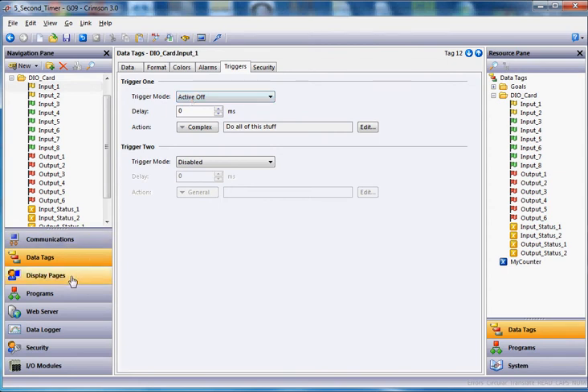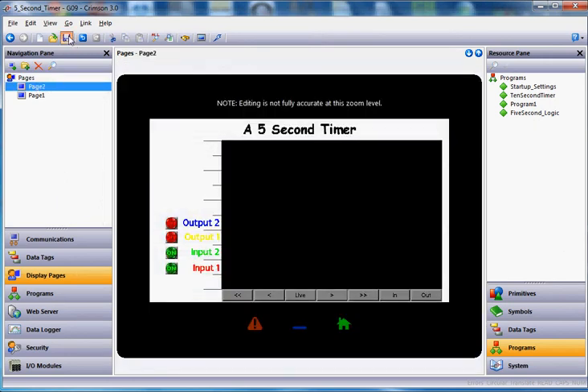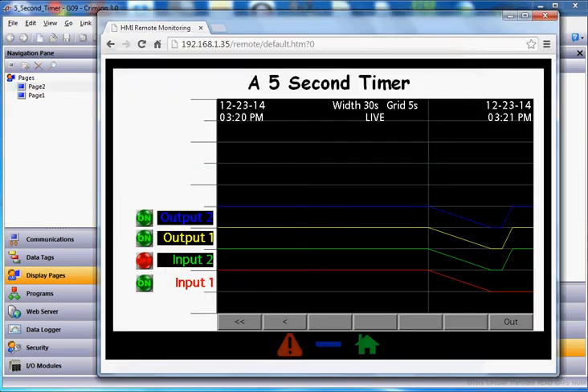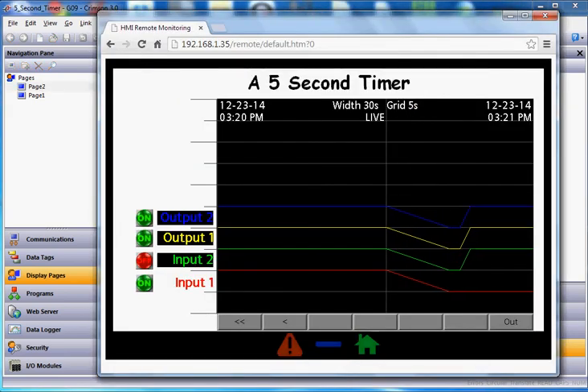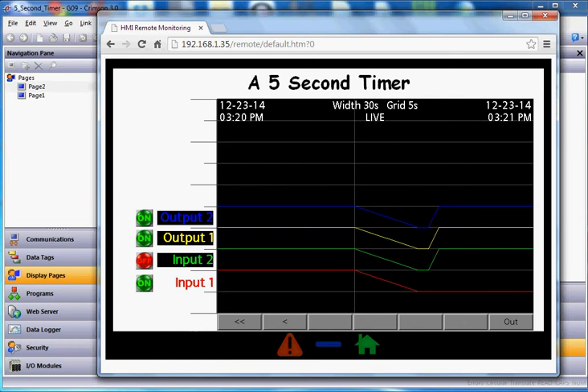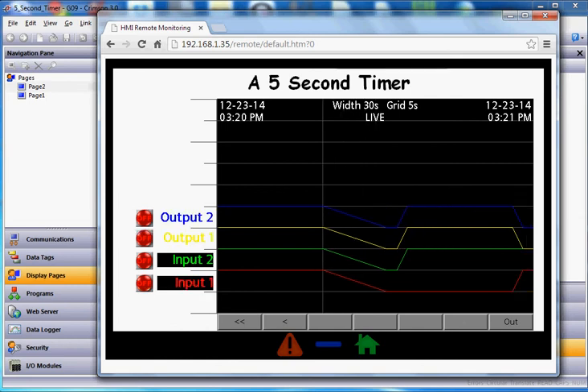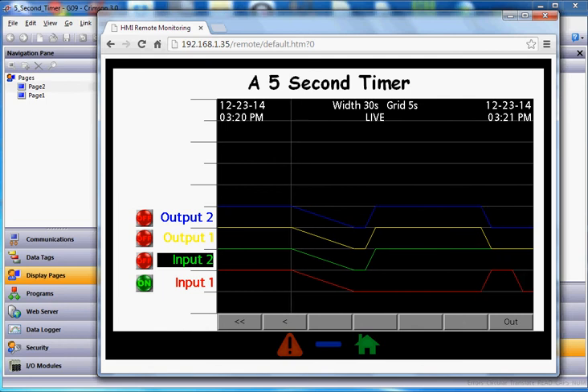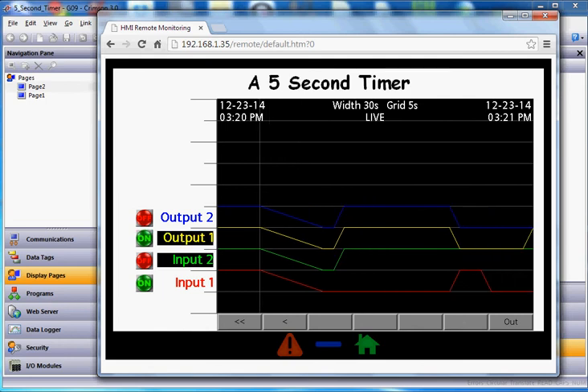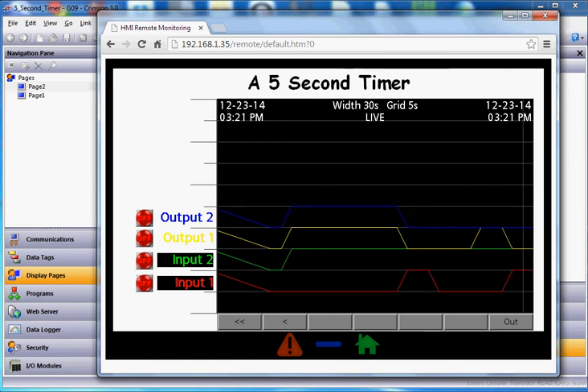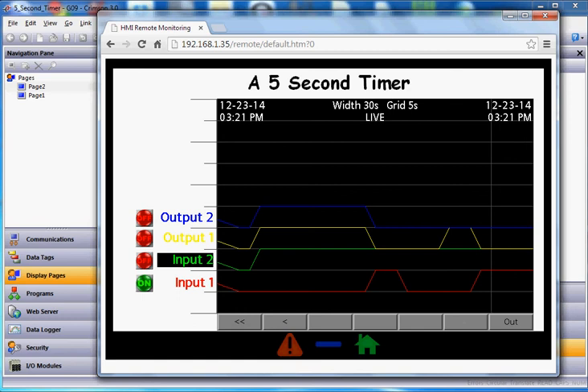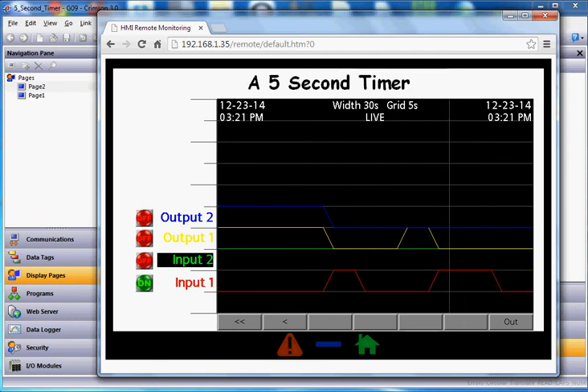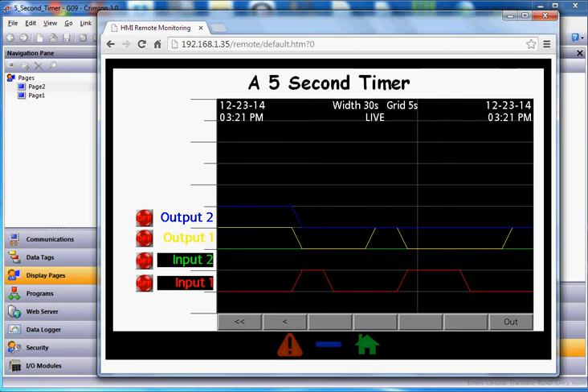So let's go back to display pages, let's go click on our page here, save our program and download it. Let's see what happens here. Let me go to the web browser so you can see the screen here. You can see right now that input one is currently in the off position. If I go ahead and squeeze the unit here, you'll see that it's on. If I squeeze it again, it's off right there. I think I know what the deal is here. My inverse logic is not quite correct here. Here I am squeezing it, and you can see, let me fix something here folks.